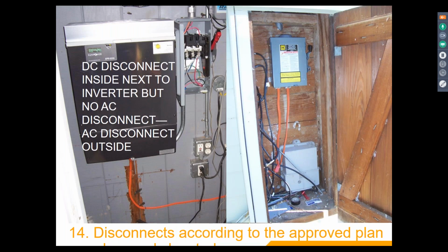Well, it's the fire guys, don't they want it? Because if you've got an AC disconnect that you can switch off outside the house and you can pull the plug outside the house, then you don't have any power, right? You can, right. Fire or whatever, do whatever you need to do. Well, that's great if you're actually doing what you think you're doing. The purpose of this switch that we're talking about here is about utility companies. It has nothing to do with firefighters. Now, the firefighter might be able to use that same switch now that we have rapid shutdown. Okay? But prior to rapid shutdown, that switch does absolutely nothing to improve safety.